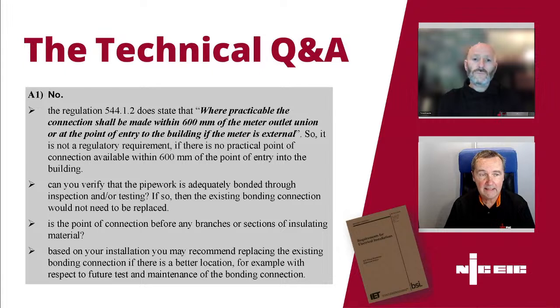So when the existing bond connection is okay, it doesn't need to be replaced. Also make sure the point of connection is before any branches or sections of insulating material, since sometimes the pipe work goes away from copper and then returns to it. Make sure it's before any insulating sections, and use engineering judgment to think about why that bonding connection is where it is.